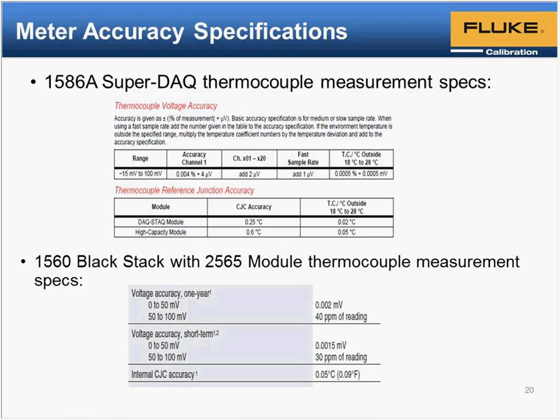Compare that reference compensation circuit, the specs for it, with one that's designed for reference level work. What I'm showing you is from the 1586A DAQ, and it might be hard to see, but for this high capacity module, the CJC accuracy is listed here, and it has a 0.6 degrees C specification. So large. The 2565 shown below, this is a reference grade thermocouple readout, and its internal CJC is 0.05 degrees C. And the difference between these two is mainly that with the 2565, the temperature sensor is right between the connectors where the thermocouple wire connects. So the connection is very, very close, and there are other things too that help make up a much lower specification.